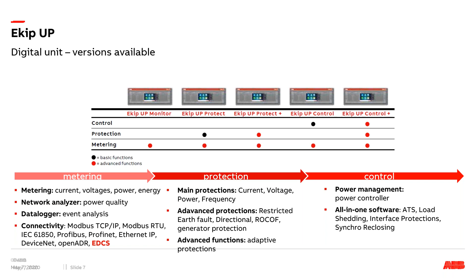As mentioned, there are measuring relay and protection equipment standards that the unit is compliant with. One of the better usages of the relay is in shipping and marine applications. It has the registration certification for RINA and DNV, which are the shipping registers, and it can operate up to 1 kV, so 1150 volt AC. You don't need any voltage transformers connected to it for voltages equal to or less than 690 volts. In terms of temperature, it can be installed in environments from -25 to +70.